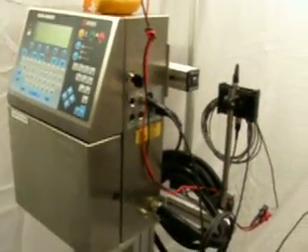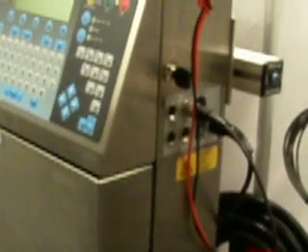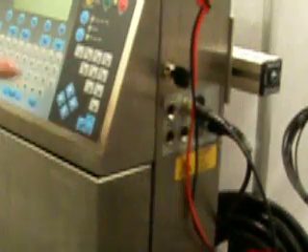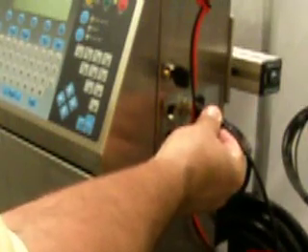Over on the right-hand side here is the conveyor stop module — that black box you see right there. The conveyor stop module plugs into the EBS 6200 via the side panel through the custom port. We have a jumper that connects from the RKM board right here into the custom port. The conveyor stop module plugs into this, and our alert light plugs into the conveyor stop module. There is also an output from the conveyor stop module that we are simulating here with the meter.